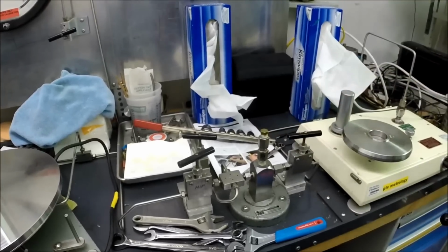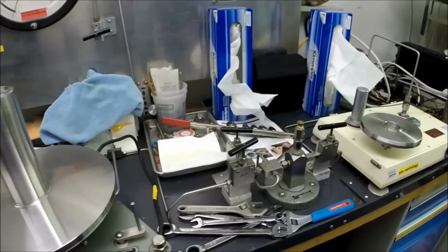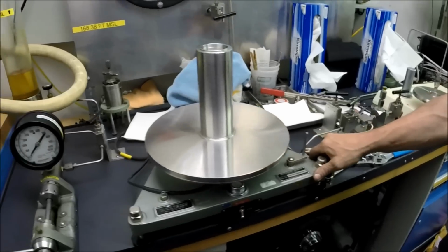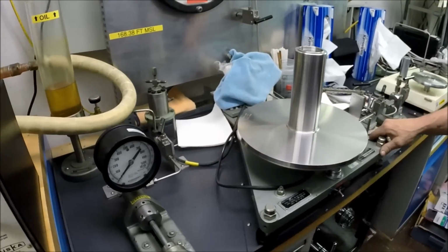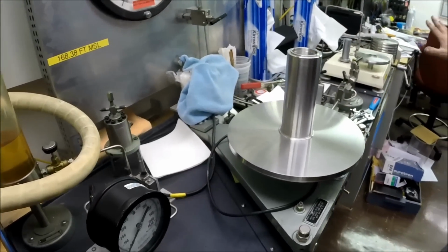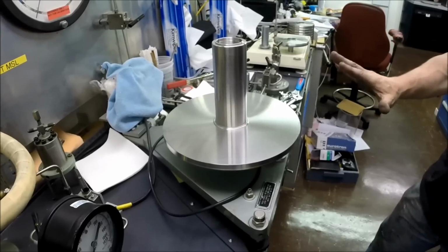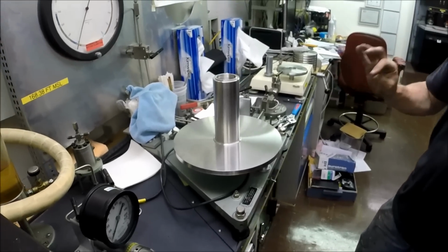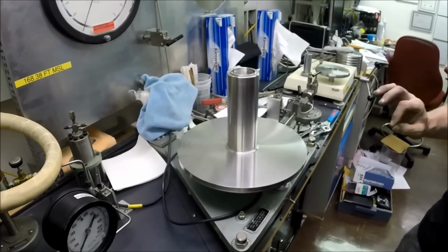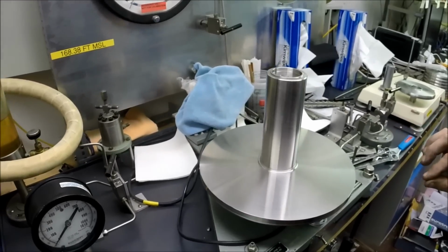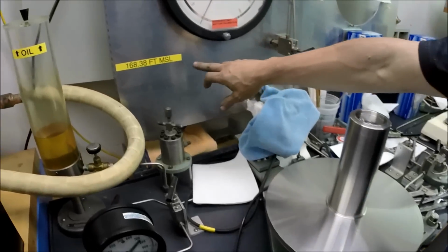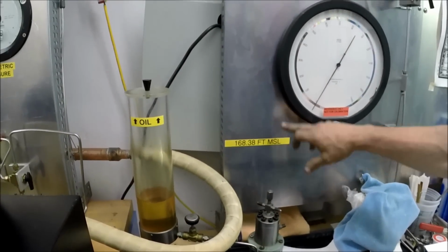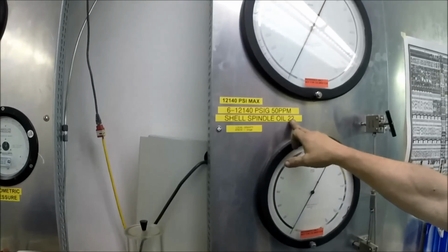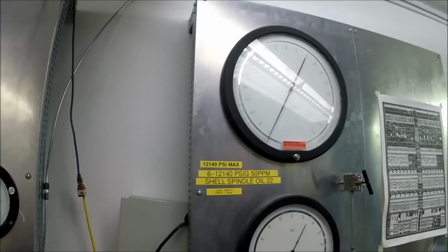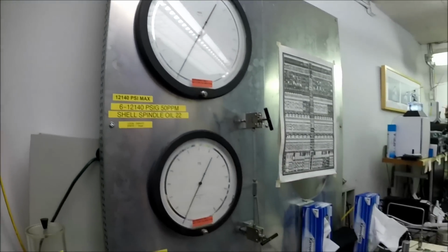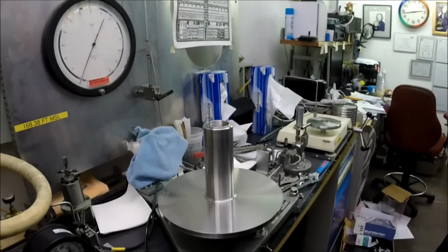If the customer needs higher accuracy, we can get approximately 50 parts per million up to 10,000 psi with this guy. It's the same principle as the first one, but each plate is individually numbered, calibrated. We know the exact weights, approximately the exact weights. There's nothing exact in calibration. We take into account our altitude, the density of the air, the temperature, the local gravity, the specific oil we're using. And if you do it all right, when you're done calculating, you should be around 50 parts per million accuracy.